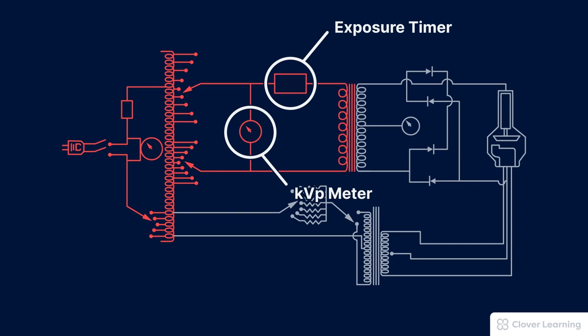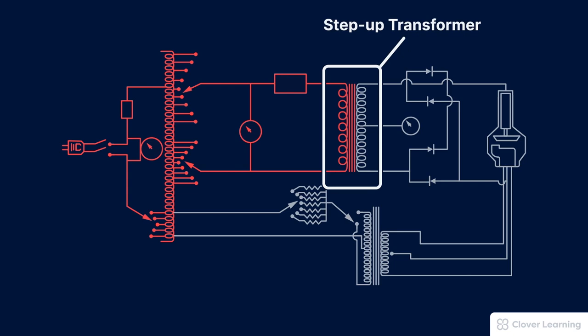The last component of the primary circuit is what we call the step-up transformer or technically the primary side of the step-up transformer. Up until this component, the electricity is still in volts, but we need the electricity to be in kilovolts. The step-up transformer increases or steps up the voltage from volts to kilovolts.